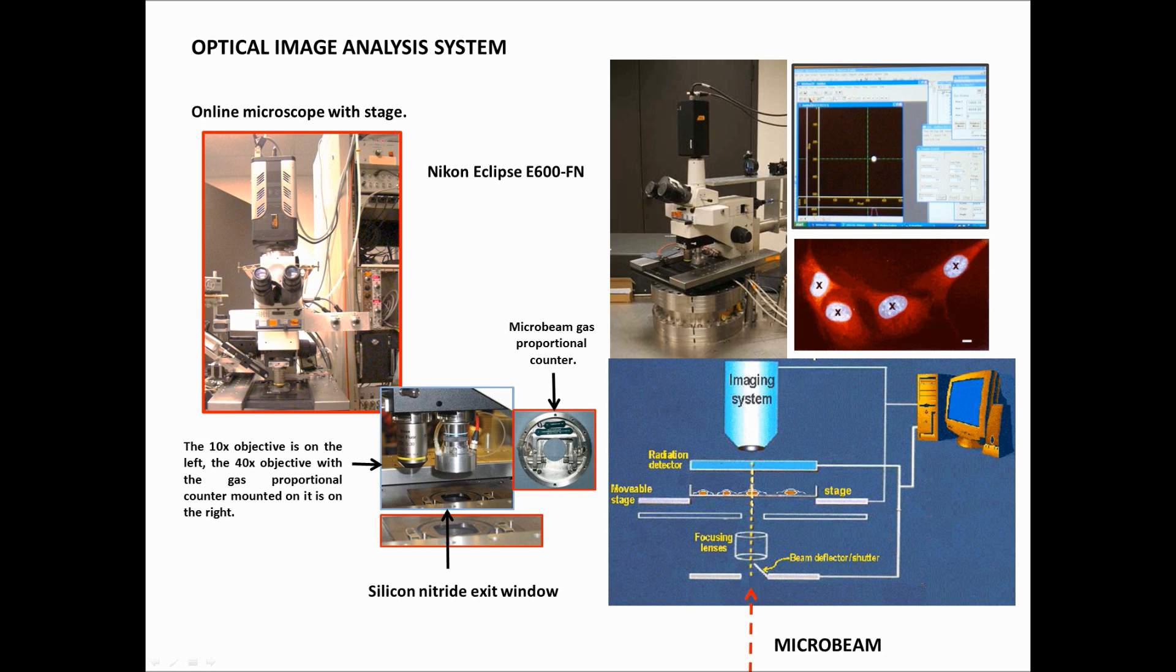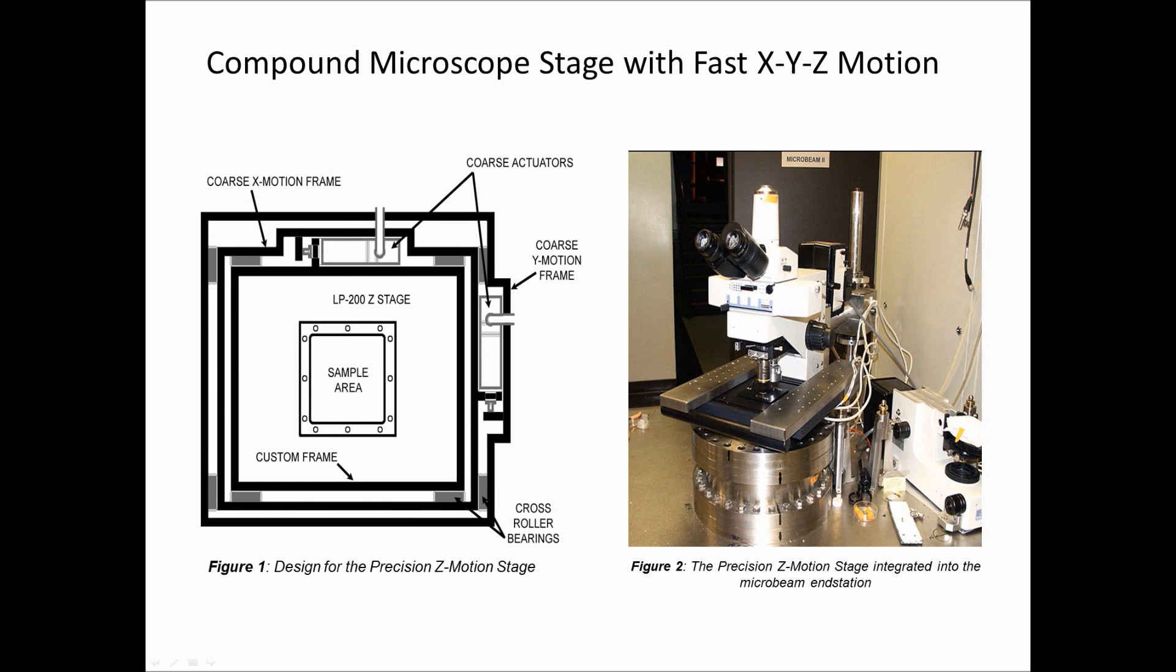This is the blown up picture of the counter. What we have is, actually when it's put together, there's a smallish aperture or eighth of an inch hole coming in the middle. So the ions are produced in the gas here as the particles come out. And off to the side here, there's a metal wire helix that is the outside surface of a proportional counter. And there's a very fine wire down the middle is where the ions are collected. And so that gives a pulse every time a particle comes through the middle of this. And that's the schematic picture of what we have. That's a bead on the system. We'll do some practicing with this so you'll see how this really works tomorrow.